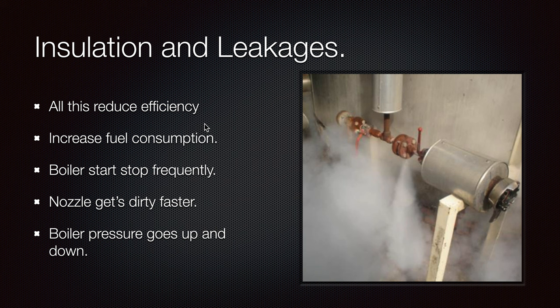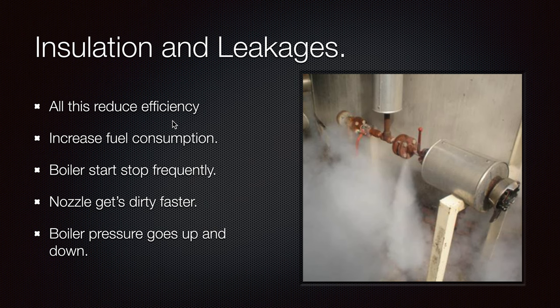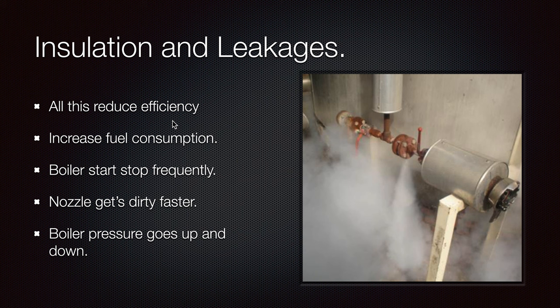Let's look at another aspect of boilers — insulation and leakages. When we have bad insulation and leakages, this will reduce efficiency and increase fuel consumption because we will have heat losses, and the boiler will start and stop frequently. This has an impact on nozzle dirtiness, and the nozzle gets dirty faster because during start/stop cycles fuel doesn't burn completely, leaving more residue in the furnace. Boiler pressure goes up and down really fast, making the boiler unstable.